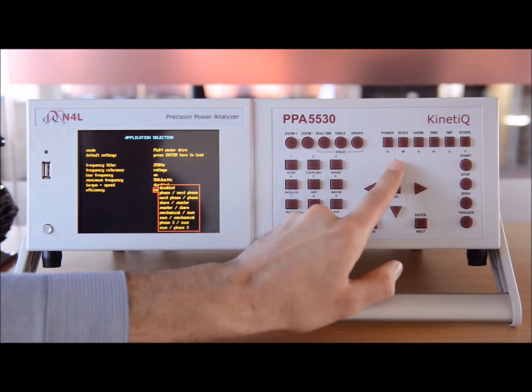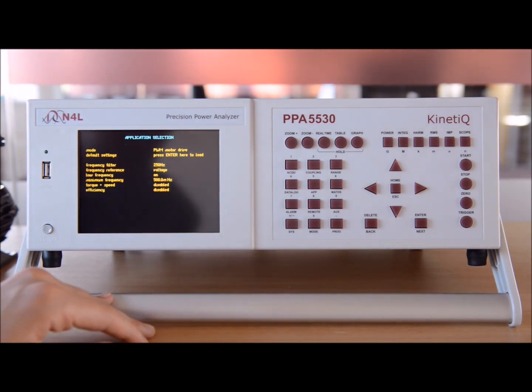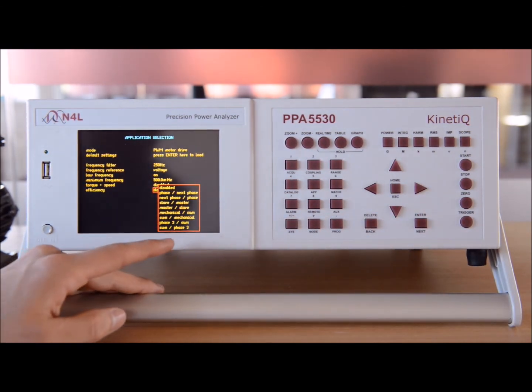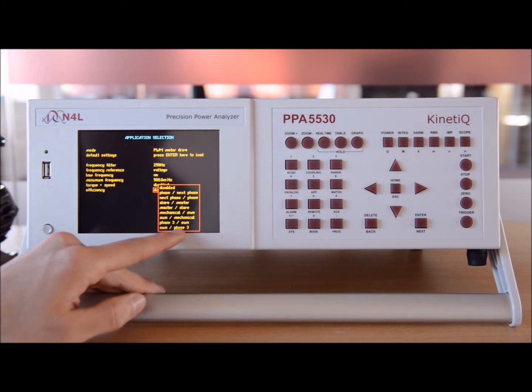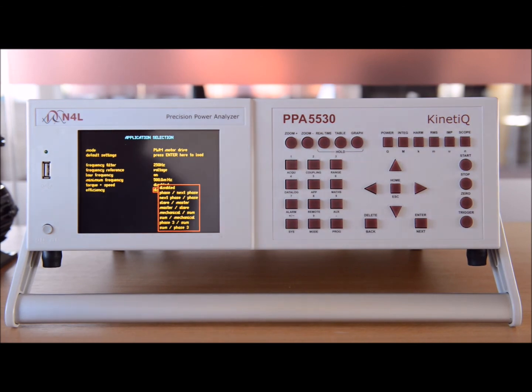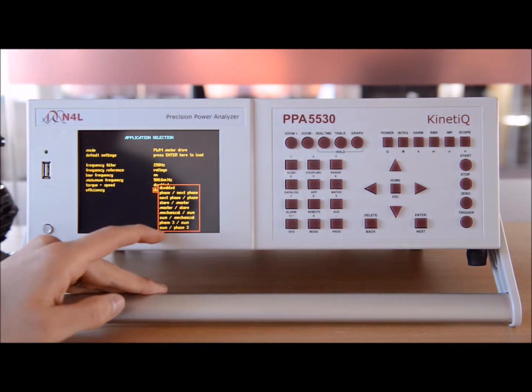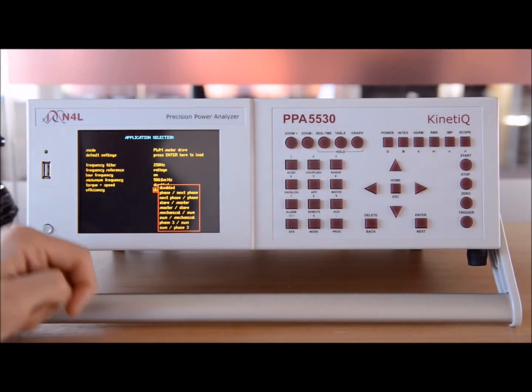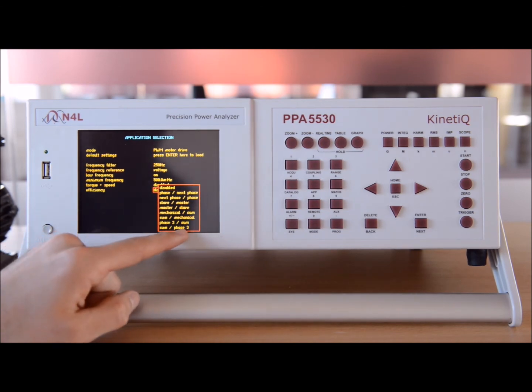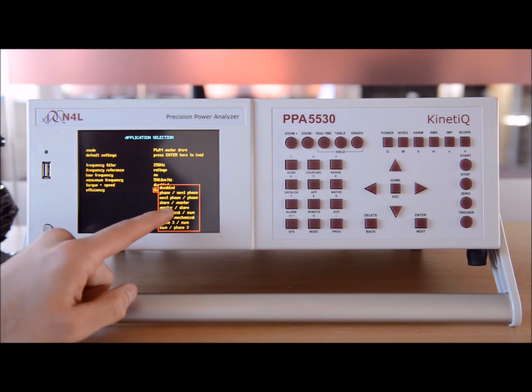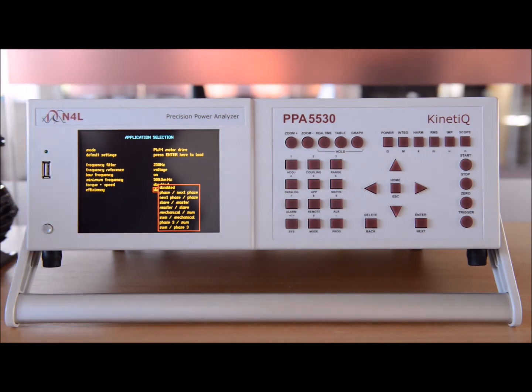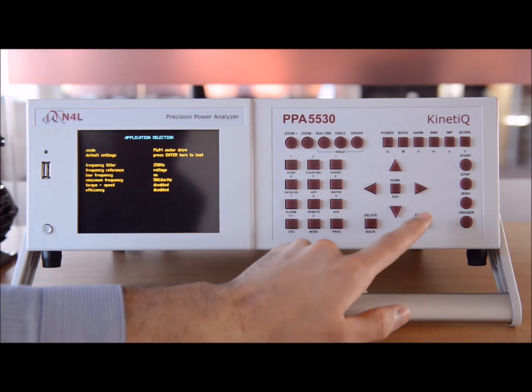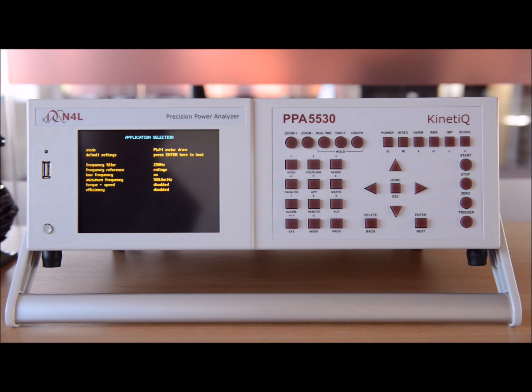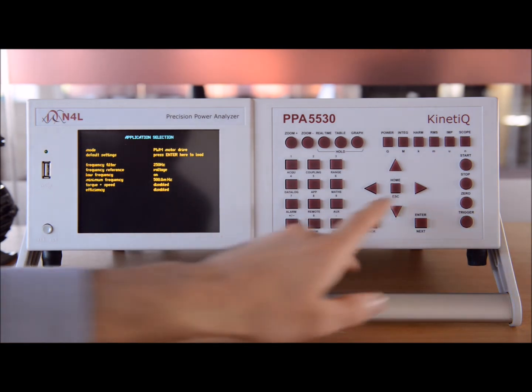Efficiency. Now we're not going to display efficiency on screen because we're going to do it via software. But you could display efficiency as, for example, sum over phase 3. So there's a method of using the third channel as the AC input or the DC bus. And you can also measure the sum on phase 1 and 2. So the 3-phase power is measured on 1 and 2, and the DC bus on channel 3. Or we can do master over slave, so we could do 3-phase input to 3-phase output with 2 3-phase analyzers. But today we're going to disable it because we're going to do the single phase from the PPA1500 through software, and the 3-phase output via the same software program. We'll show you that in a short while.